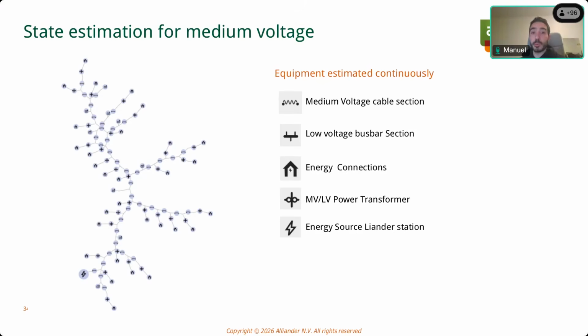The equipment we focus on for further investigation, among many others, are the medium voltage cables, the low voltage busbar sections, the energy connections representing large clients and small clients (households) in the low voltage grid, and the power transformers at the points where you go from medium voltage to low voltage. Then there's the energy source from the stations, considered the in-feed or energy dump within that route.